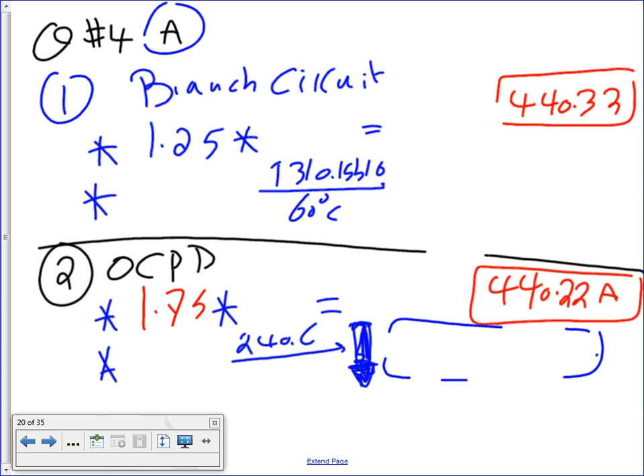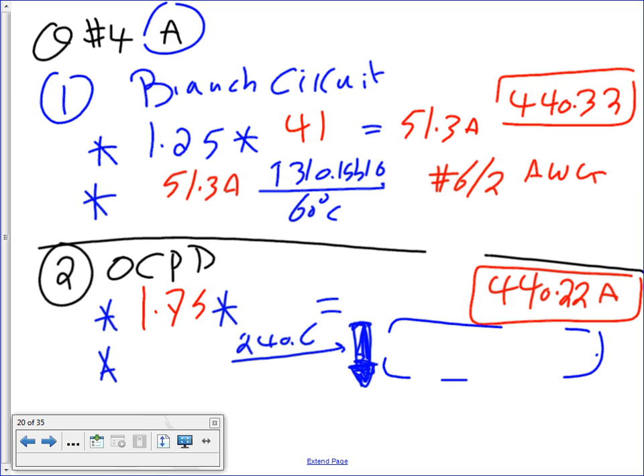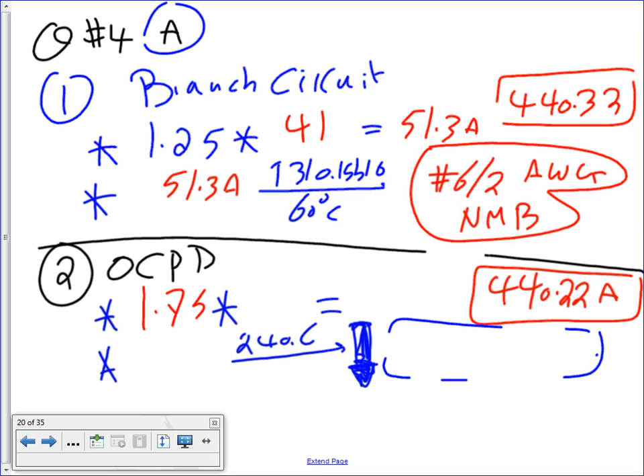Branch circuits. For branch circuits, guys, 440.33, it tells you it's a continuous load, so magic number. If you ever have to guess when you size branch circuits, guys, always guess 1.25. 41, that will get you 51.3 amps. You take your 51.3 amps. Since we're using Romex, then we have to go to the 60-degree column. Okay, that will get you number 6-2, 2 conductors, AWG NM-B cable. That's it, 1.25.